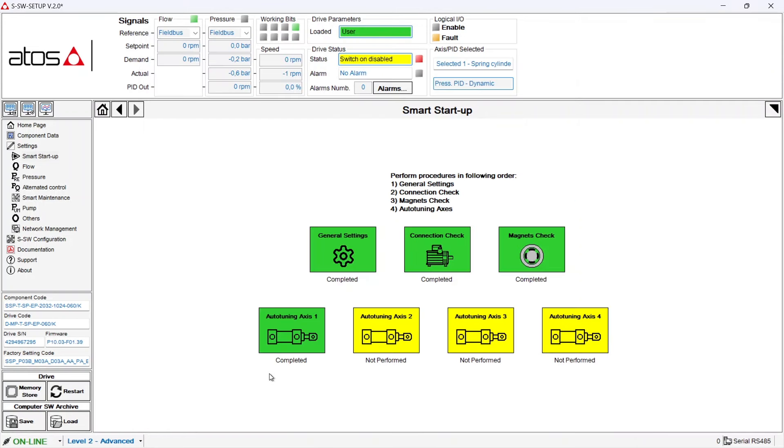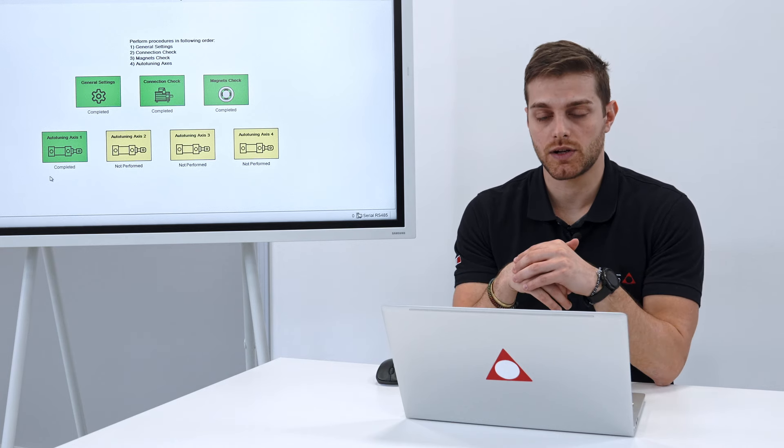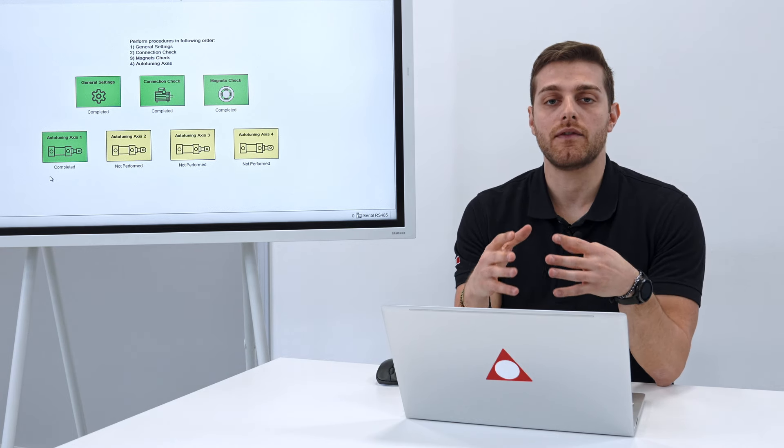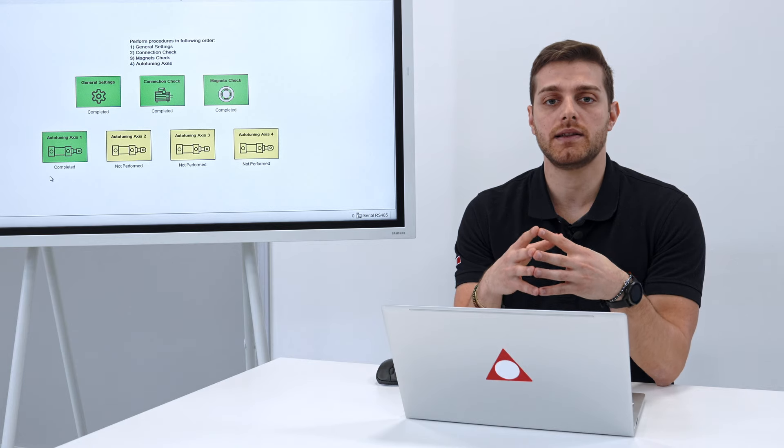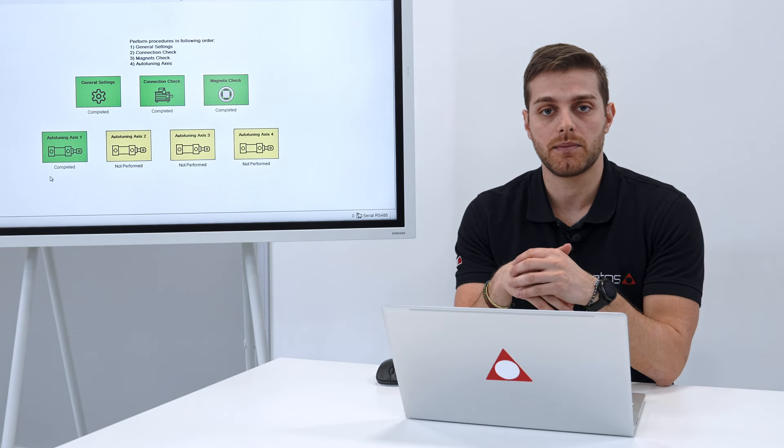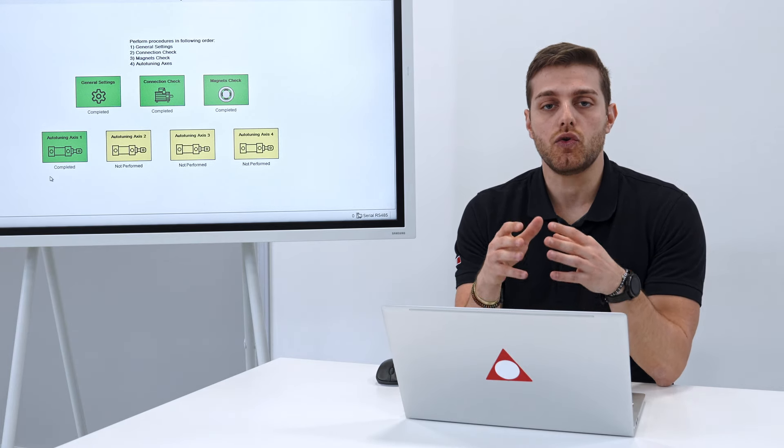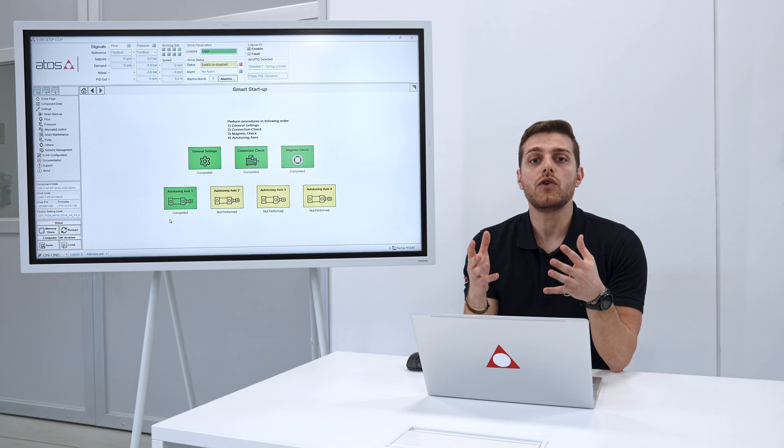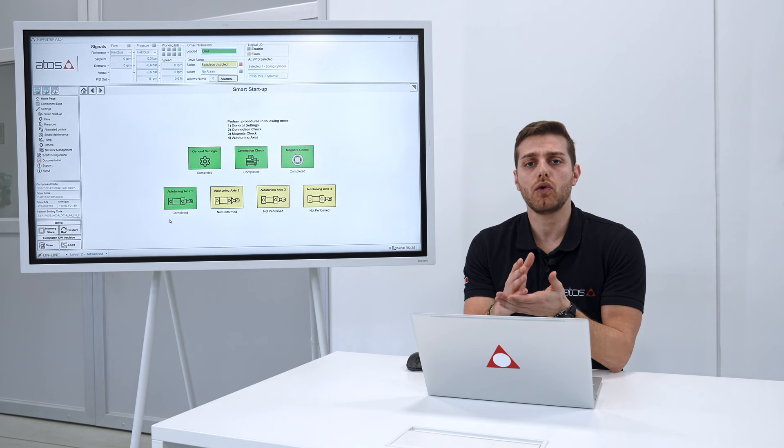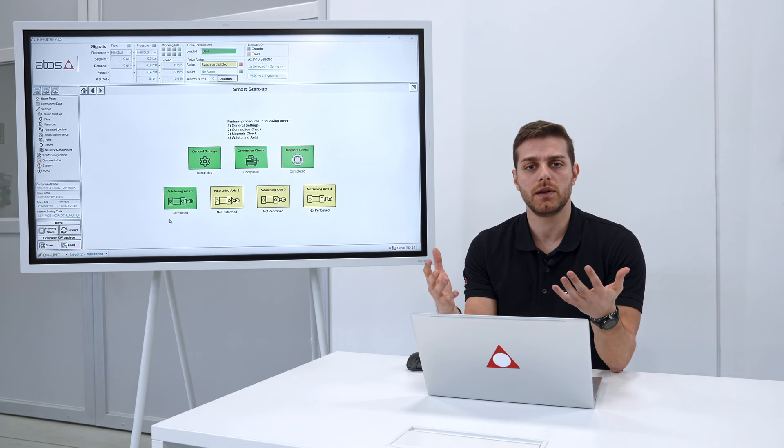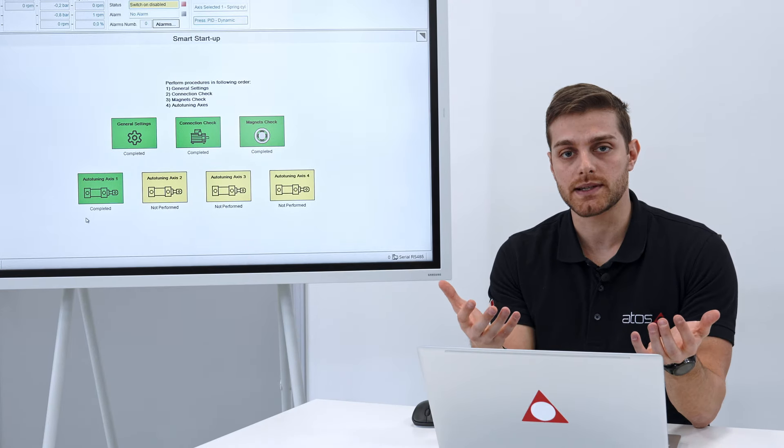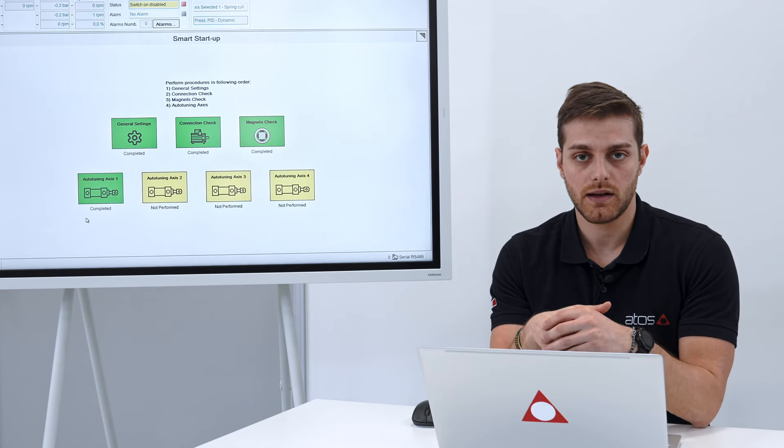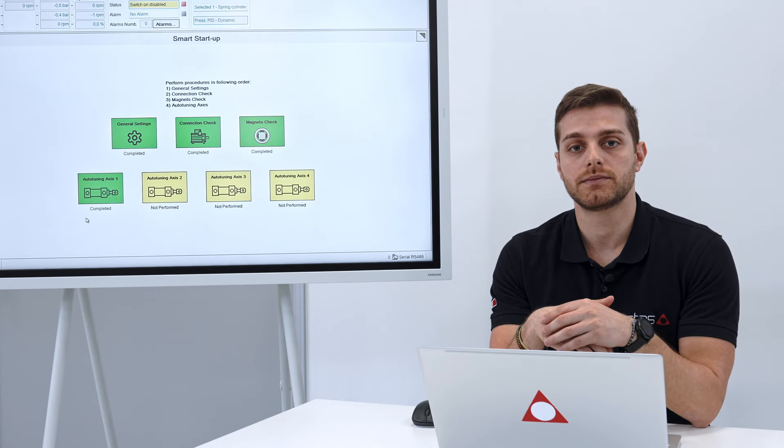Industrial machines have usually more than one cylinder and each of them with their different size and different oil volume. So each of them needs their own optimal pressure PID. Our multiple axis functionalities allow to have four different sets of parameters saved inside our servo pump. So you can select among them and you can have all the movements of your machine optimized. How to select among them? Through field bus if you have it, otherwise through digital input.